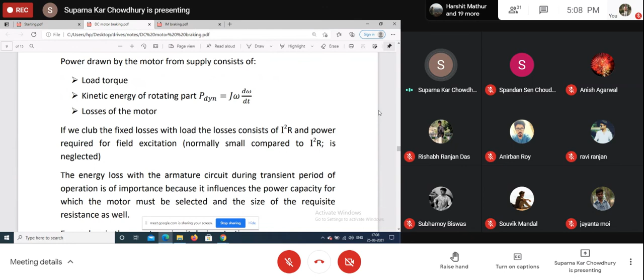So basically, the fixed losses can be clubbed together with the load. That will not change really with load, but what will change with current is the I square R loss, the variable loss. This is very important because that affects the temperature rise. So separately, we can derive the energy loss due to the armature circuit losses. That will be, say, for the starting process, t starting is the time. So the loss will be integral 0 to t start of I square R dt.